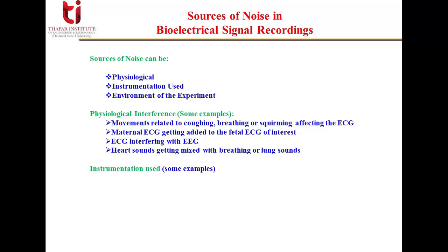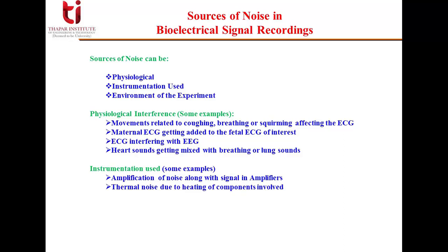Now next is the noise due to instrumentation used. Due to the weak levels of most biomedical signals at their source, high amplification factors are required. So electronic noise in the instrumentation amplifier also gets amplified along with the desired signal. There can also be thermal noise due to heating of instruments or components. So they contribute to the instrumentation noise.